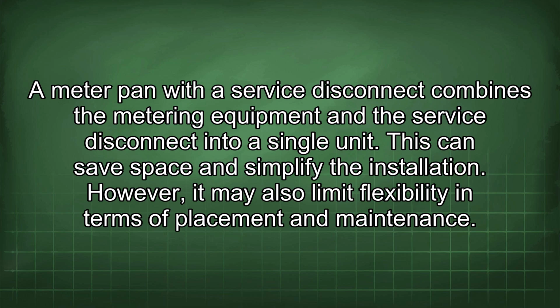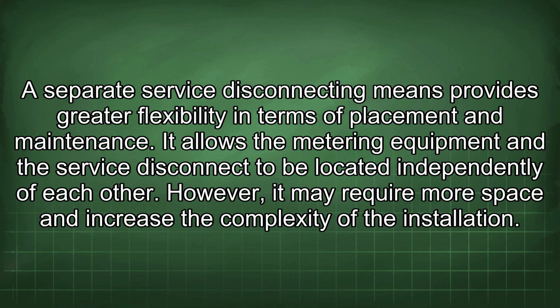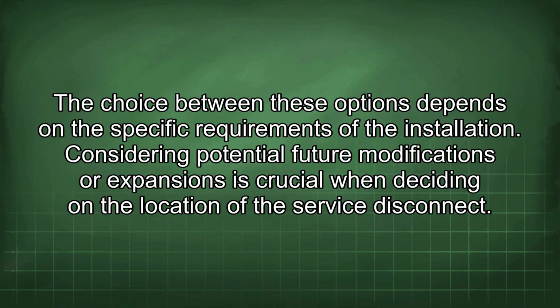However, it may also limit flexibility in terms of placement and maintenance. A separate service disconnecting means provides greater flexibility in terms of placement and maintenance. It allows the metering equipment and the service disconnect to be located independently of each other. However, it may require more space and increase the complexity of the installation. The choice between these options depends on the specific requirements of the installation.